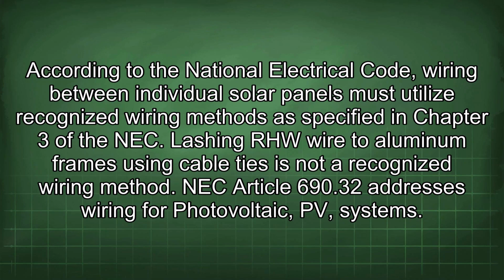According to the National Electrical Code, wiring between individual solar panels must utilize recognized wiring methods as specified in Chapter 3 of the NEC. Lashing RHW wire to aluminum frames using cable ties is not a recognized wiring method. NEC Article 690.32 addresses wiring for photovoltaic PV systems.